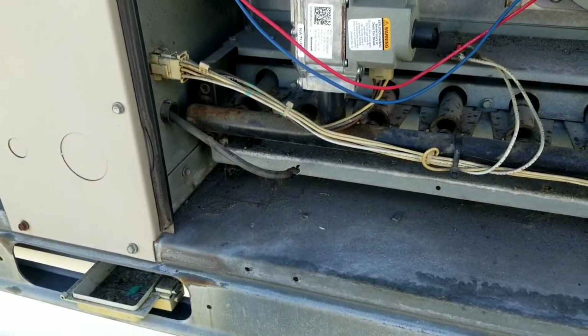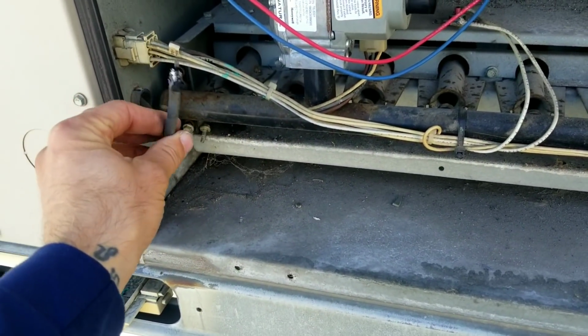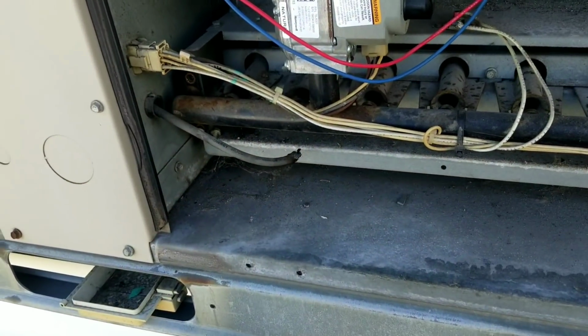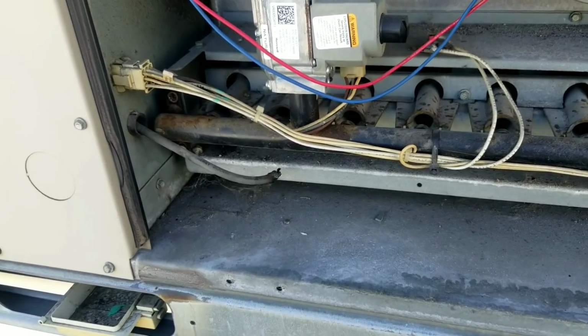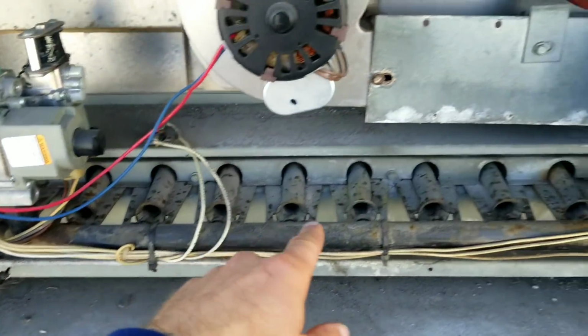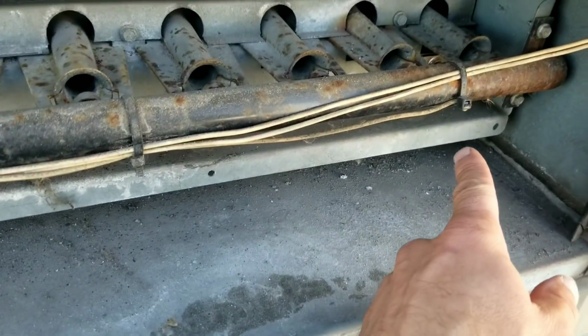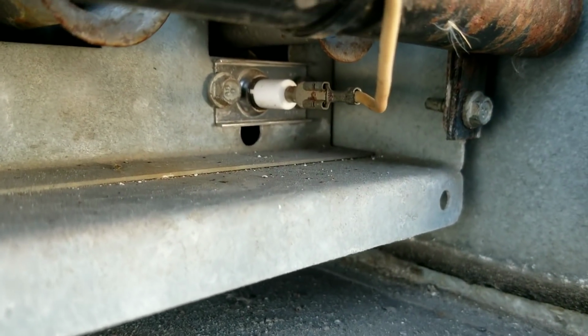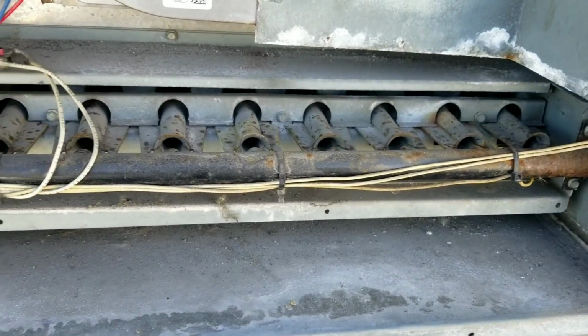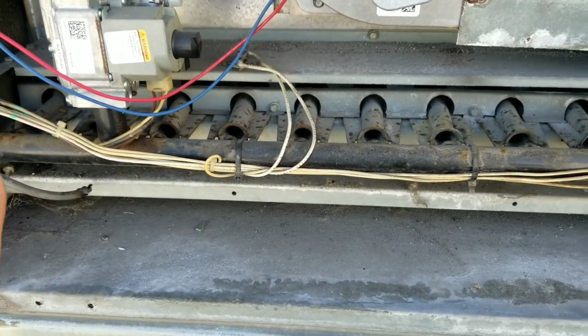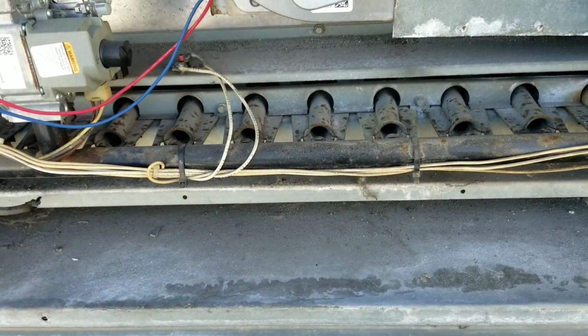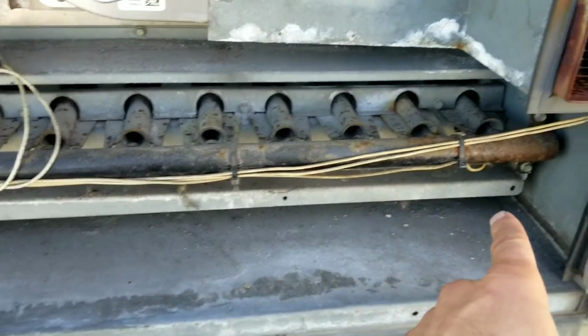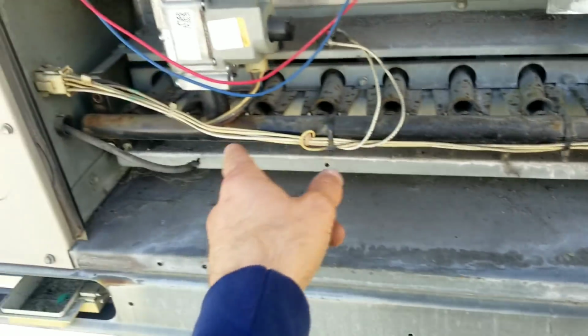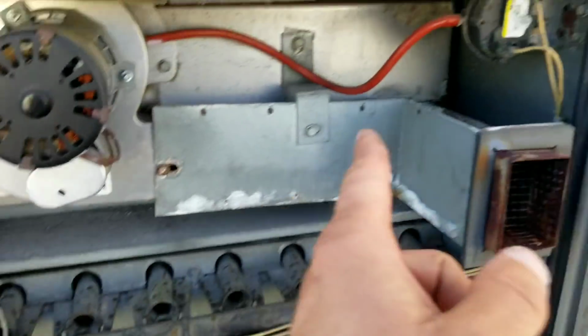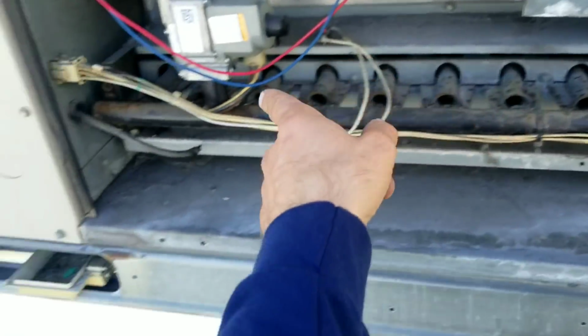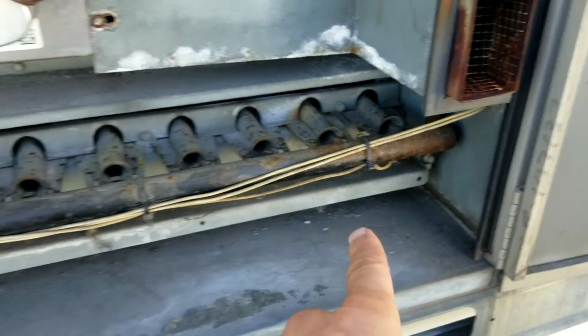But the way I look at it, there's no point in replacing just this wire and leaving the 10-year-old spark igniter in there. There's no point in doing the wire and the spark igniter and not doing the flame sensor, which is rusted out as well - not terrible, but it is rusty. There's no point in doing half of the components that make this thing heat. In the middle of winter, I don't want to come back and replace this flame sensor after I've replaced the spark igniter months ago, or replace a pressure switch after I replaced an igniter and flame sensor. Makes no sense.